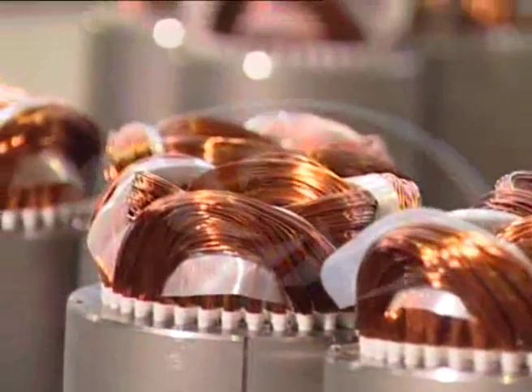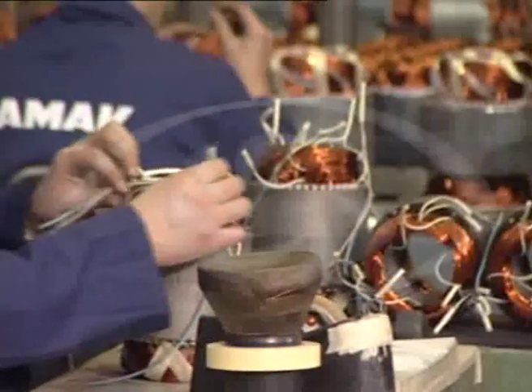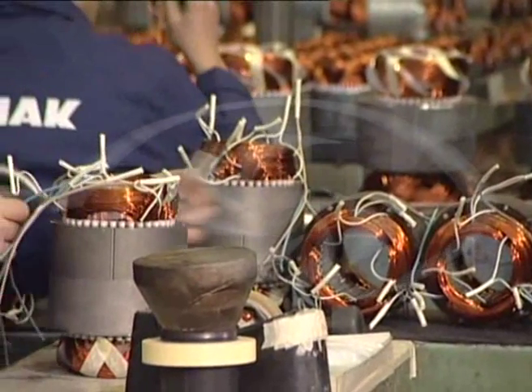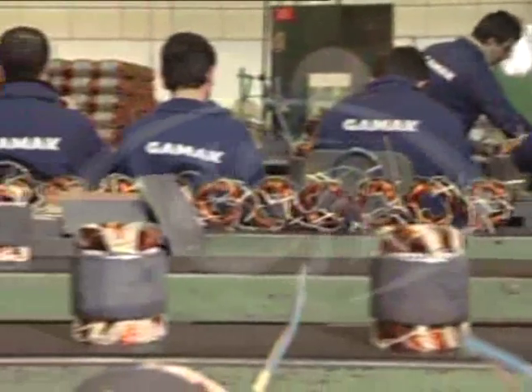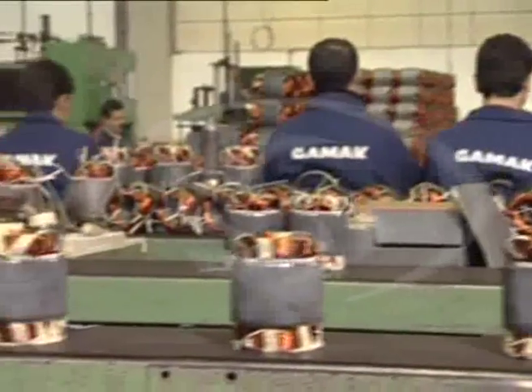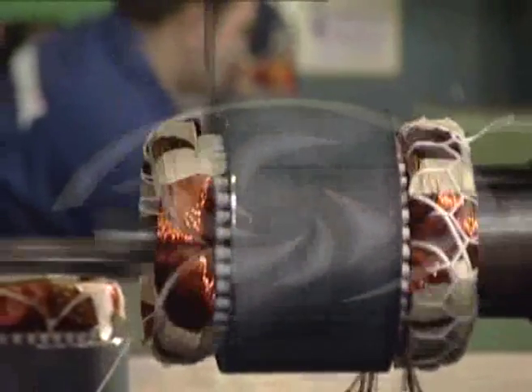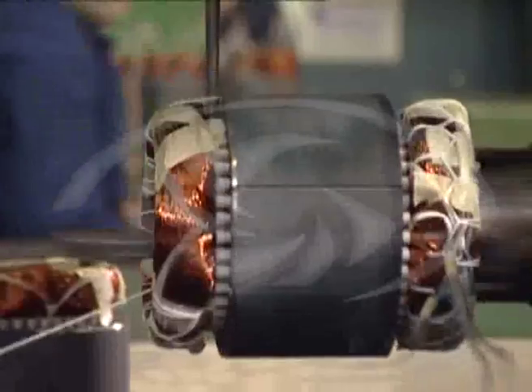Phase insulation is made in all motors, irrespective of size. Leads are connected to the conductors and insulated with sleeves upon brazing of the joints. Upon lacing of the winding heads, the stators are submitted for testing.